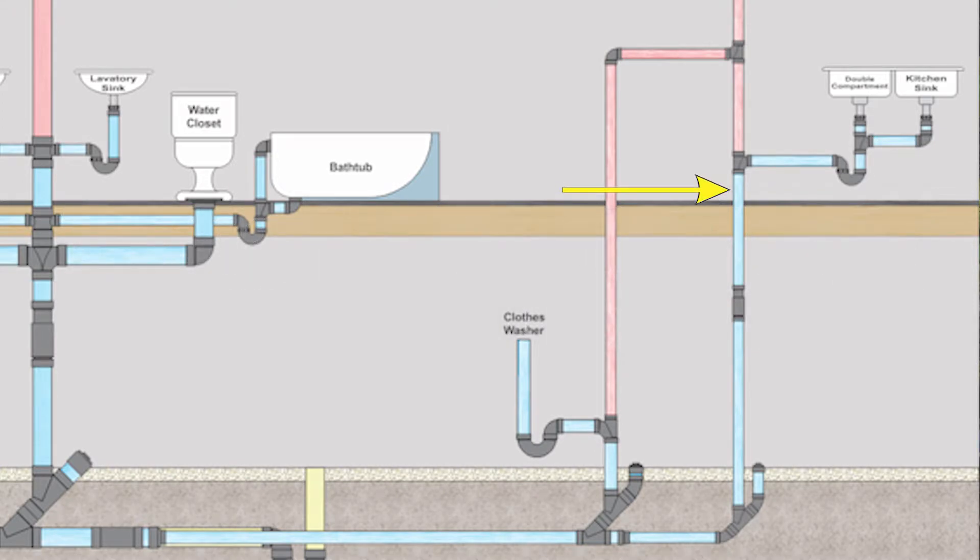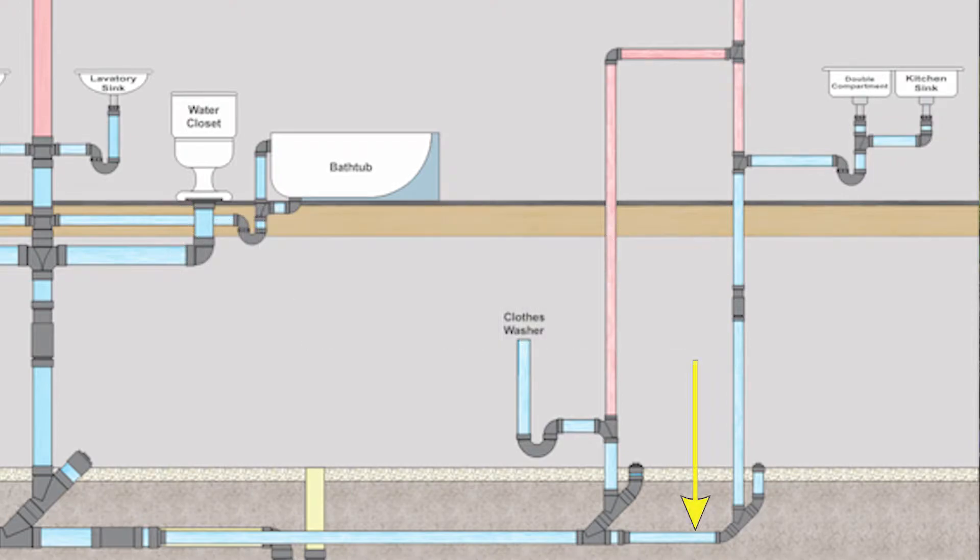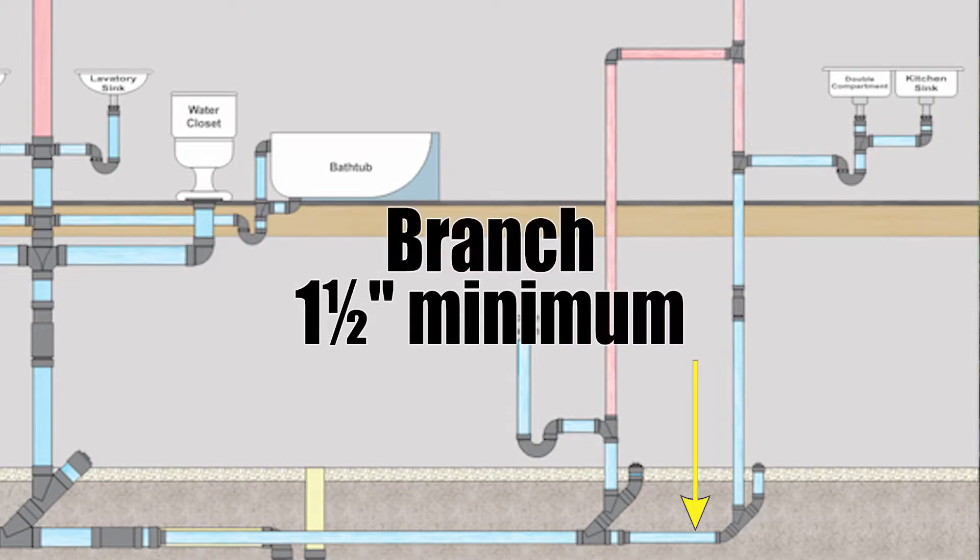Now look at the drain though, it drains down through a full story that makes that a soil or waste stack. Now the only thing draining into that soil or waste stack is the kitchen sink so it too will be one and a half inches minimum. At the base of that soil or waste stack we have a pipe that goes horizontal that's called a branch. That is only serving that kitchen sink so it too will be one and a half inches minimum.